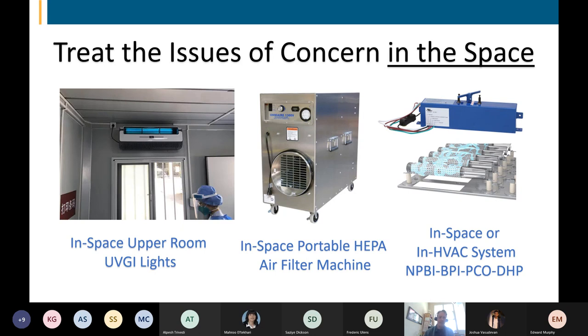We cannot have UVC light being directed downward into an occupied space with human beings because it can be detrimental to our health. These devices then typically will rely on either mechanical or natural ventilation in the space to help circulate the pollutants of concern through the field of luminance that's been directed upward so that over time, it has enough contact time, enough dose to be able to inactivate those contaminants within the air that are in direct contact with the light source. Now, a device like this, for example, might cover approximately 200 square feet of floor area.